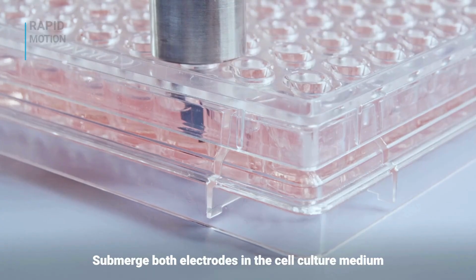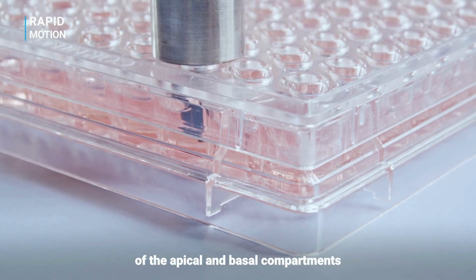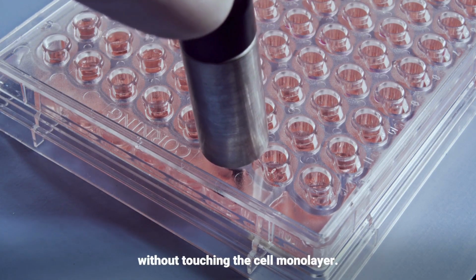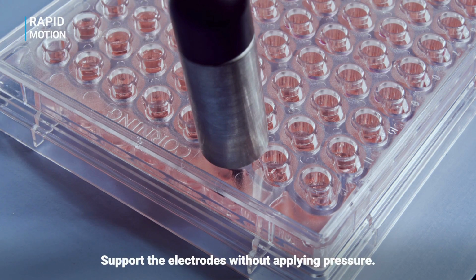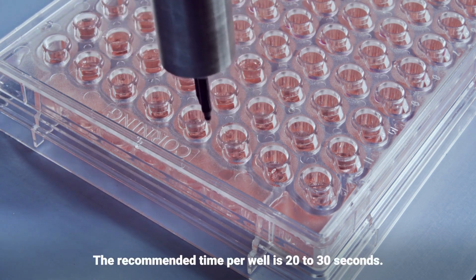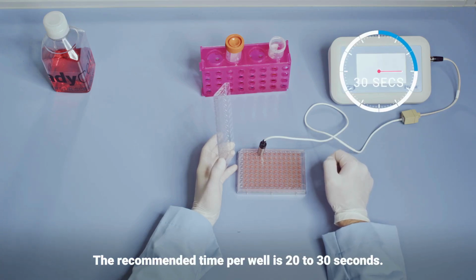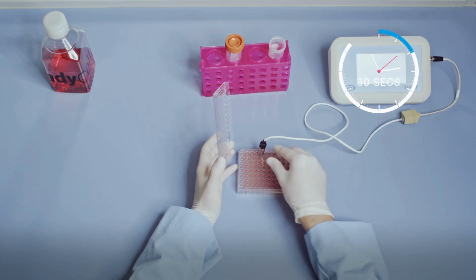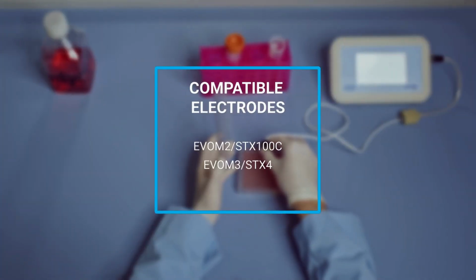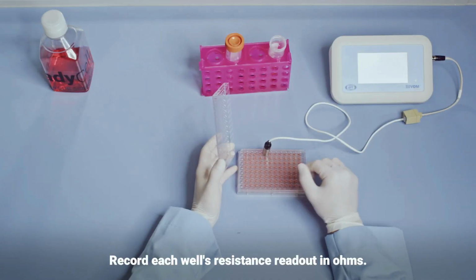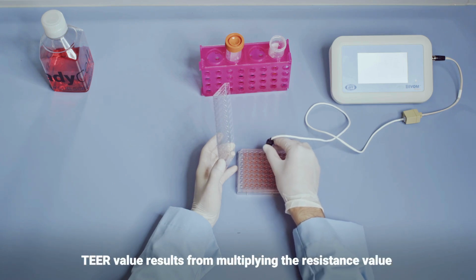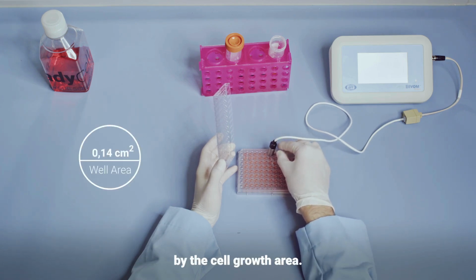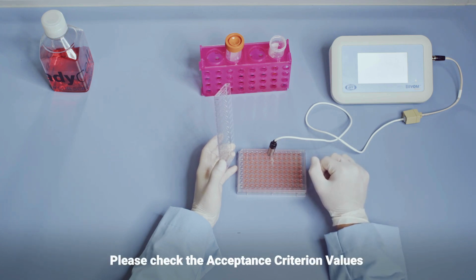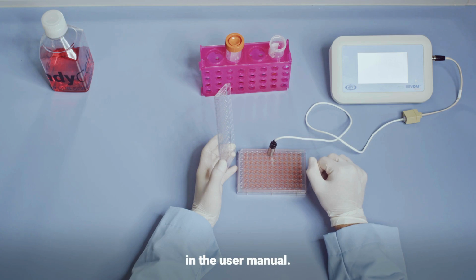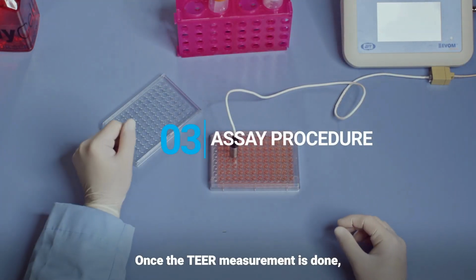Submerge both electrodes in the cell culture medium of the apical and basal compartments without touching the cell monolayer. Support the electrodes without applying pressure. The recommended time per well is 20 to 30 seconds. Record each well's resistance readout in ohms. TEER value results from multiplying the resistance value by the cell growth area. Please check the acceptance criterion values in the user manual. Once the TEER measurement is done, you can perform your assay.